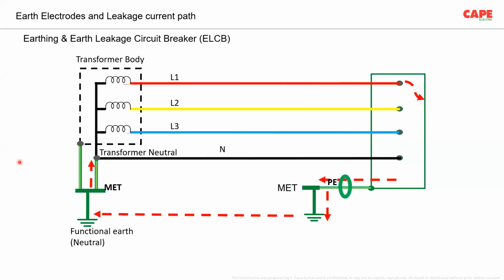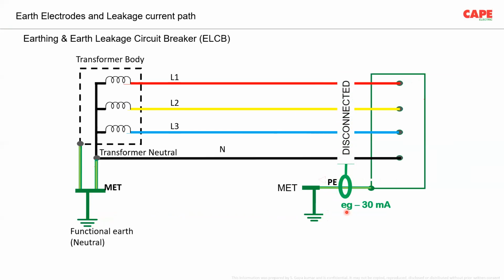Now, what you should understand is the principle of operation of an earth leakage circuit breaker. The earth leakage circuit breaker measures the current which is flowing through that particular wire, the earth wire, and this measurement is connected to a sensing mechanism and a mechanical switching operating device. Whenever the current through this wire is more than the limit, for example 30 milliampere, this device will sense that current and disconnect the supply, or your ELCB will trip. As soon as your ELCB trips, the leakage current is gone, the shock hazard is gone. This is the simple method of operation of an ELCB.